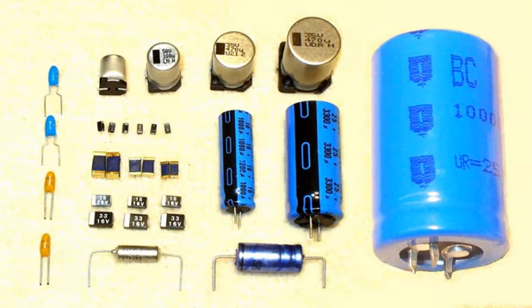Large-size capacitors, especially large sizes and high-voltage types, should be individually guarded against sudden energy charge of the whole capacitor bank due to a failed specimen.